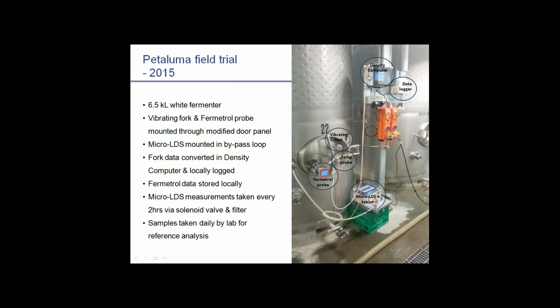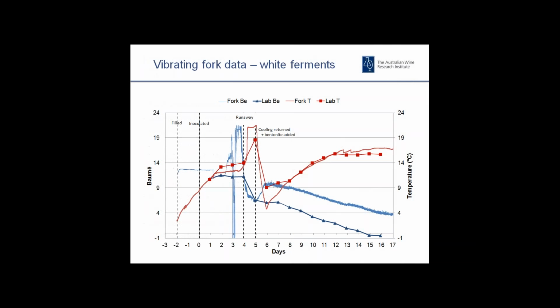This is the density computer that I talked about. So the vibrating fork data is collected and converted in here, and then we've got a data logging unit here to collect the data from that particular sensor. The micro LDS sensor is situated in the bypass loop here, so we've got a hose connected to the sampling port, and we had a 2-hour measurement cycle on that, so a sample taken every 2 hours through an automated solenoid valve and an inline filter. And we had daily samples taken by the lab for reference analysis.